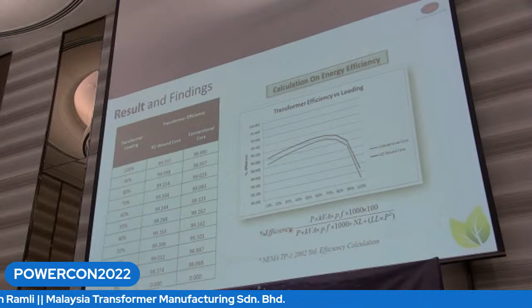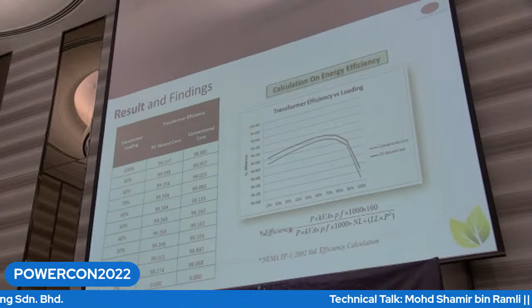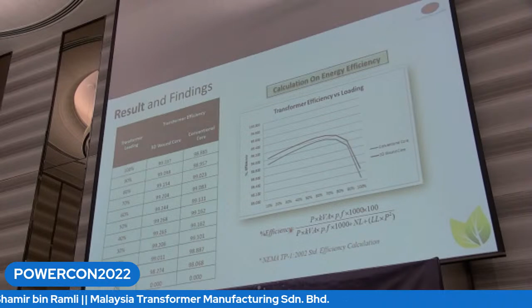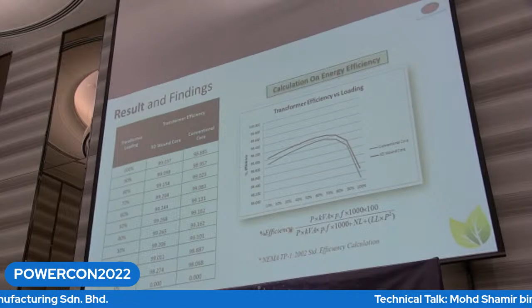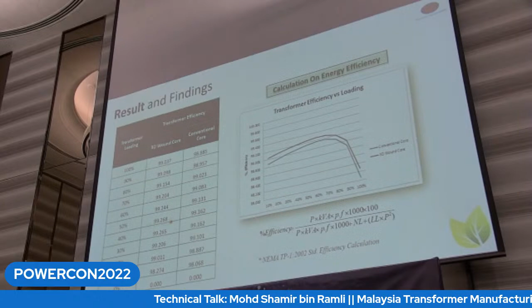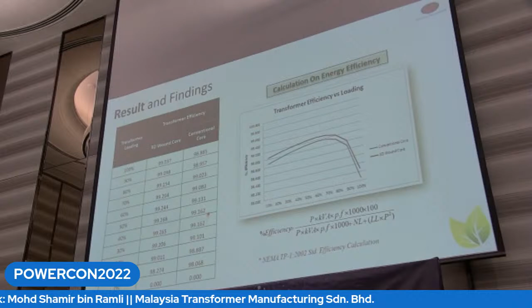In terms of the efficiency, the slide shows the chart of the transformer efficiency versus the loading. Of course, for a normal distribution transformer used in the network, the loading is around 50 to 60%, and this is where the transformer efficiency is being looked at. At 50%, the 3D wound core efficiency is around 99.268%, versus the conventional transformer at 99.162%.